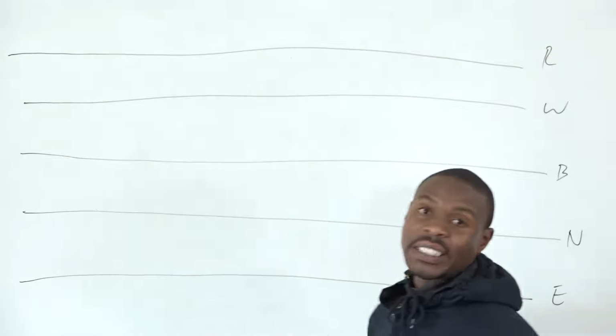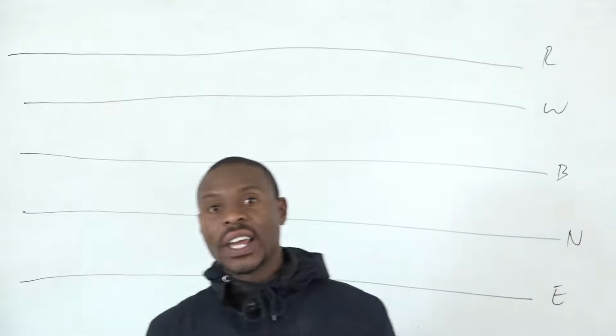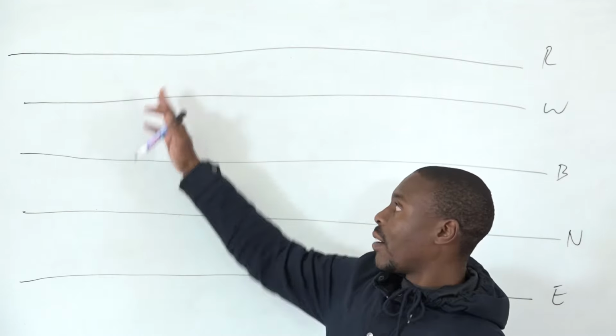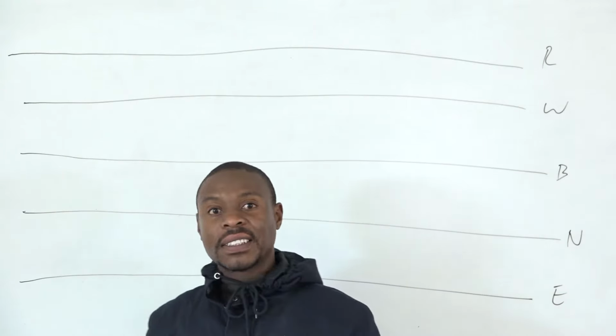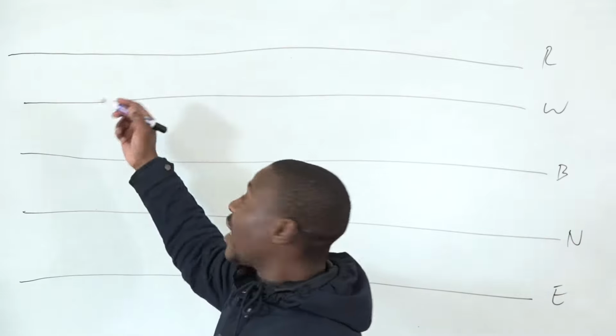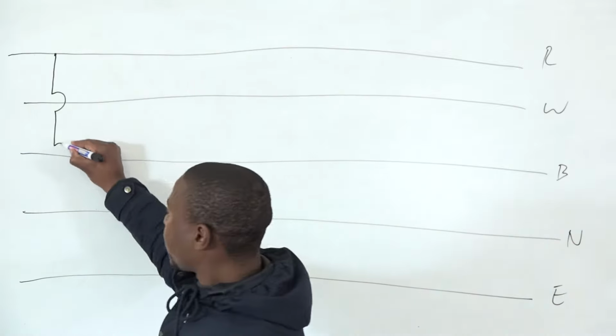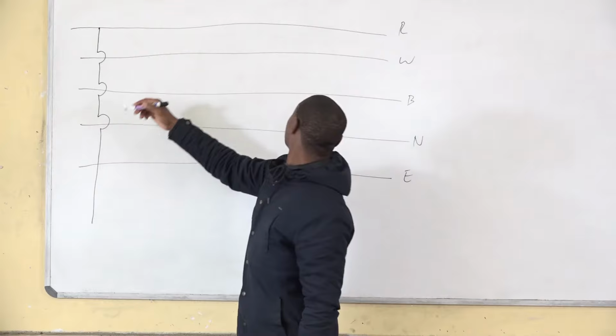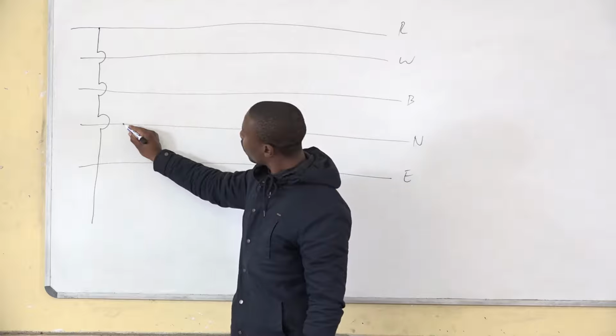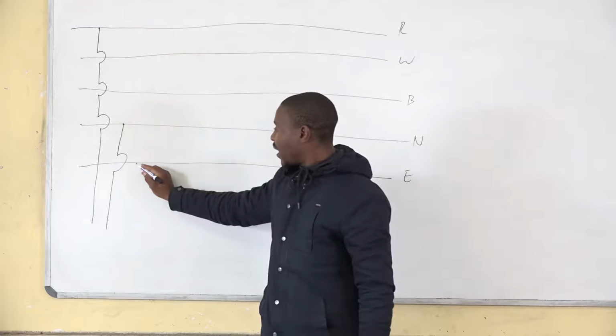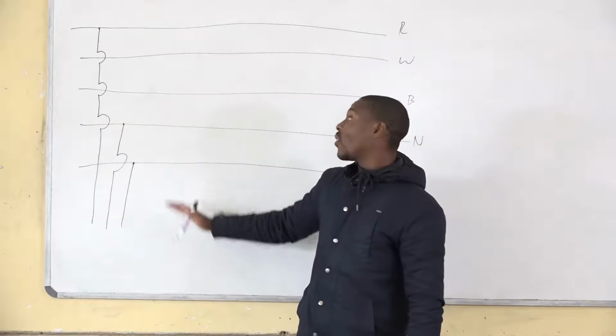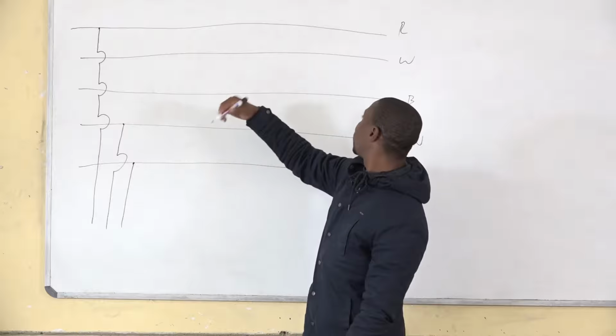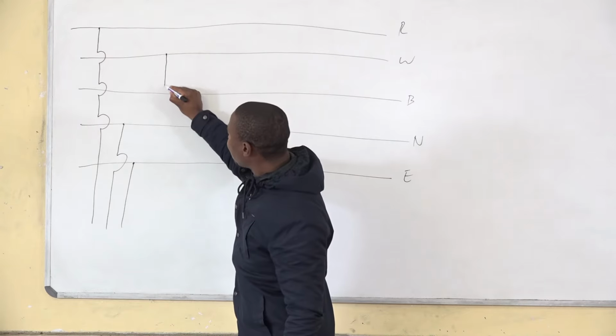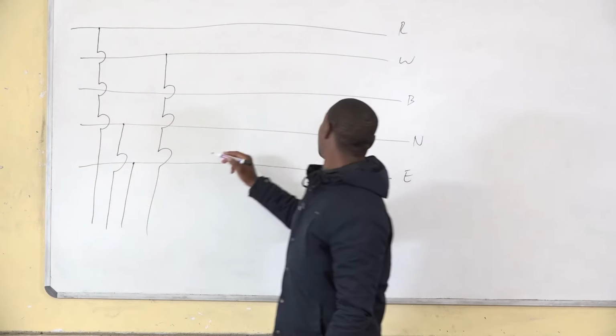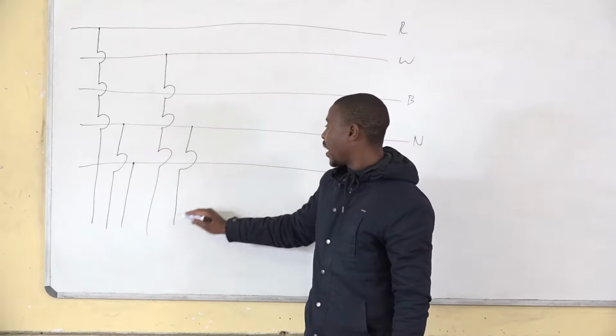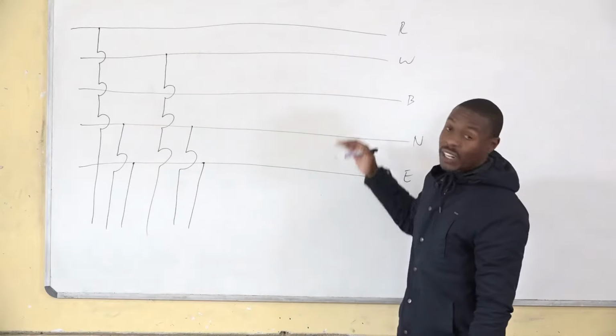So I'll make just an example. Let's say you are supposed to supply a location. You will have 10 houses being supplied on one phase, then another set supplied on the other phase, and so on. They take 10 houses from the red phase, straight to the house. Then they take the neutral straight to the house. Then they also take earth. Then they don't repeat the same thing on the same phase. They must now go to the second phase, which is the white phase. They tap line 1 again, then take neutral and earth again. Then they do it again on the blue phase.